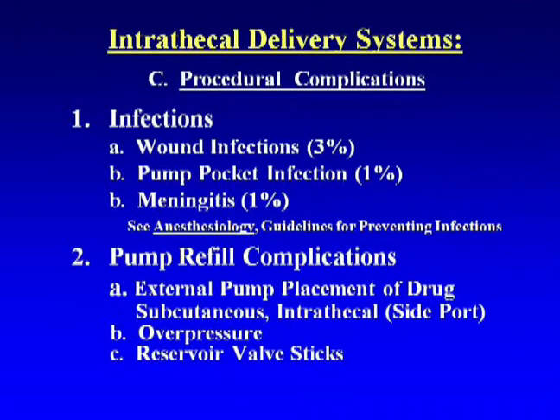This incident prompted the pump manufacturers to send a warning letter distributed to everyone dealing with these neuroaxial systems. The warning emphasizes making sure you are in the reservoir septum, and guidelines were provided for what to look for.